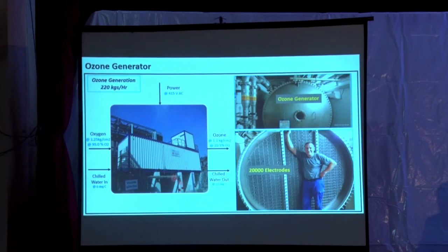This is our typical ozone generator. The generator is within the container, with the oxygen inlet and ozone outlet. Oxygen pressure will be maintained around 1.25 with 95% purity of the oxygen. At the outlet, we will produce 10.5% ozone. This is the water inlet and outlet. This is the power supply.